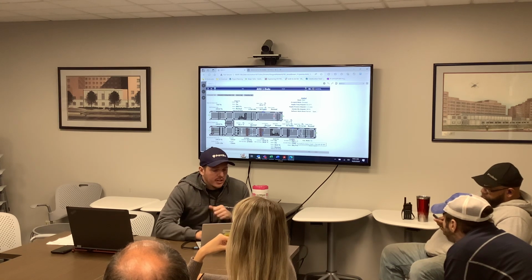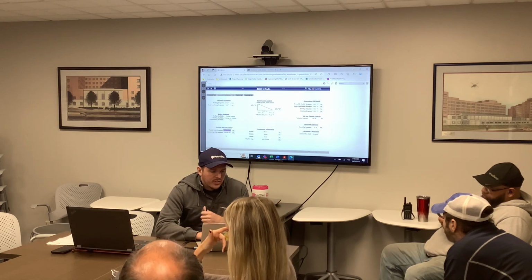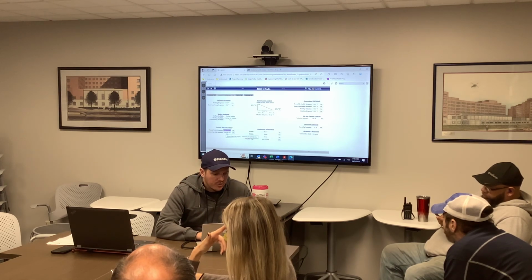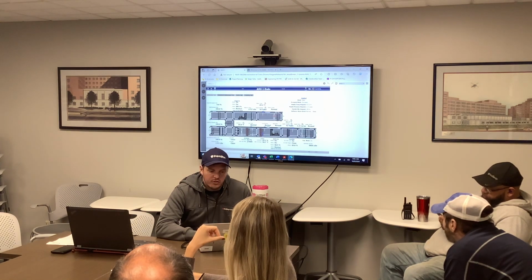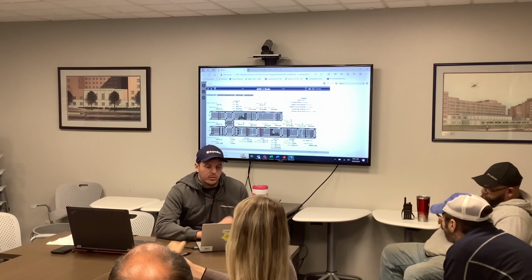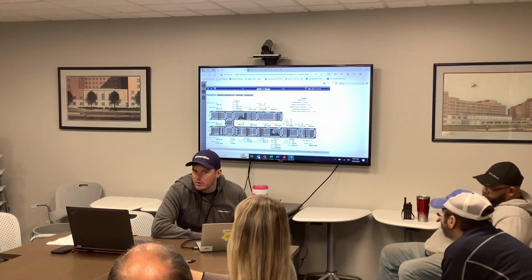What else? Does anyone have any other questions? There is a couple set points, this return fan CFM differential. This is set by the balancer, I wouldn't mess with that. It controls your return fan speed, and it's just trying to maintain a flow between OA and discharge.